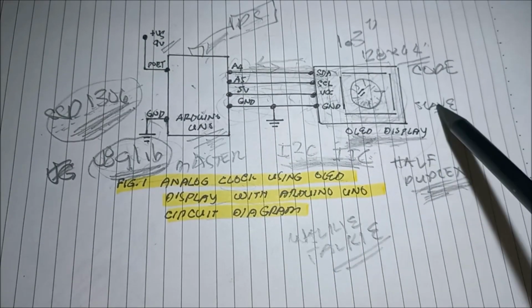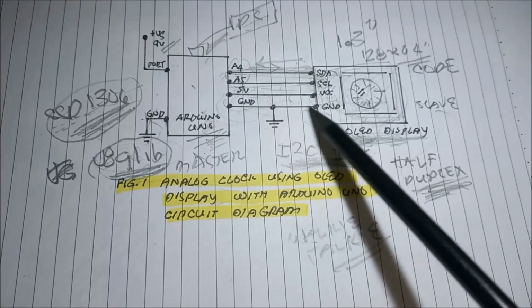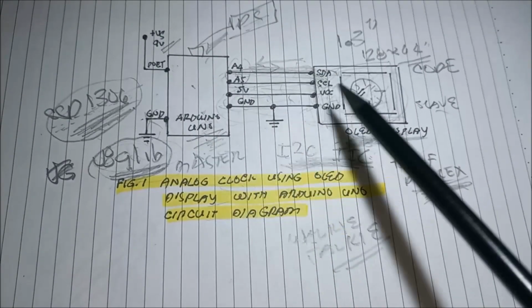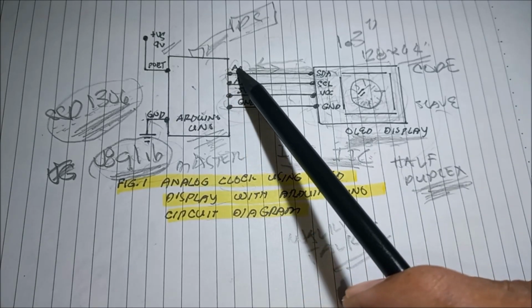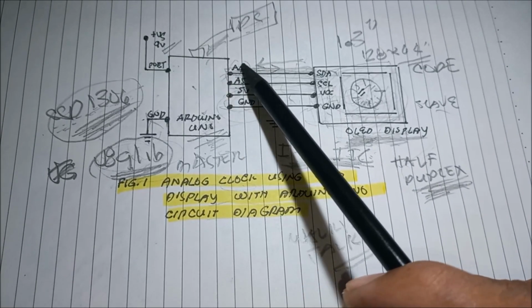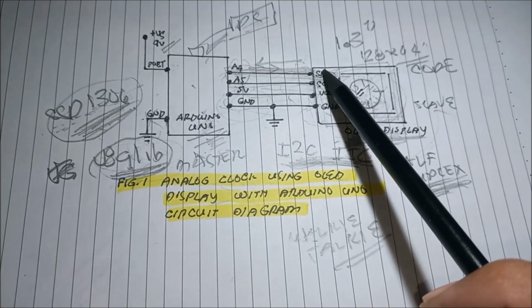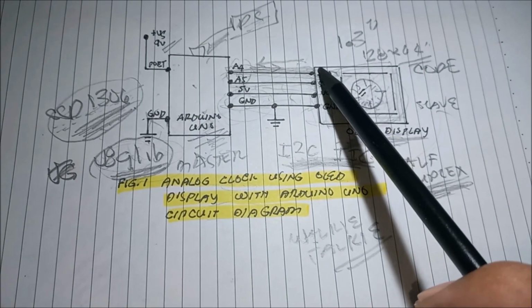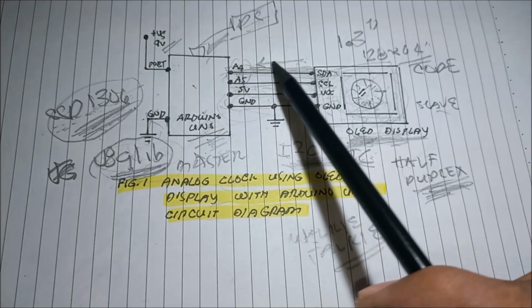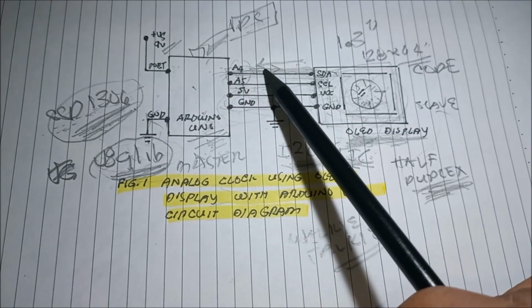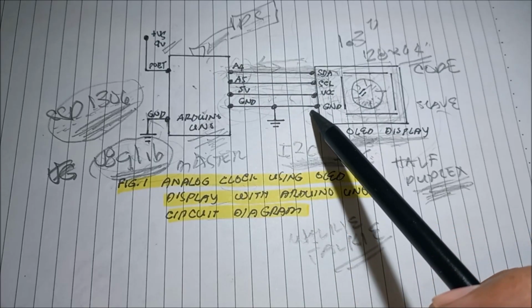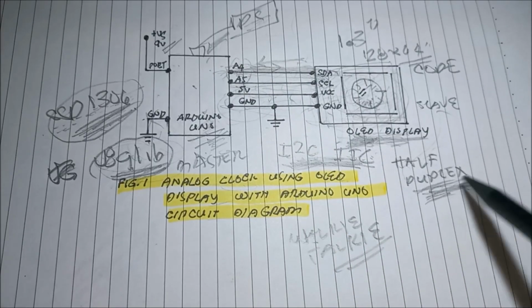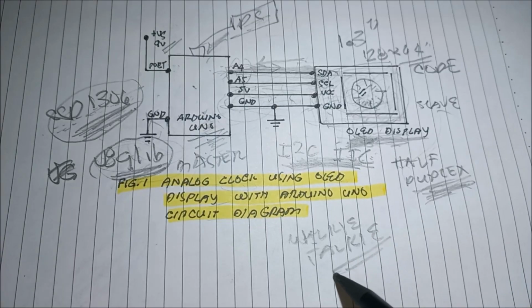And then for the communication mode, how the master and the slave communicate, it is half duplex: transmitting from this side to the other end, and then receiving. This becomes the transmitter now. It transmits to the other, which receives. So transmit and receive, one at a time. So that is half duplex, just like a walkie-talkie.